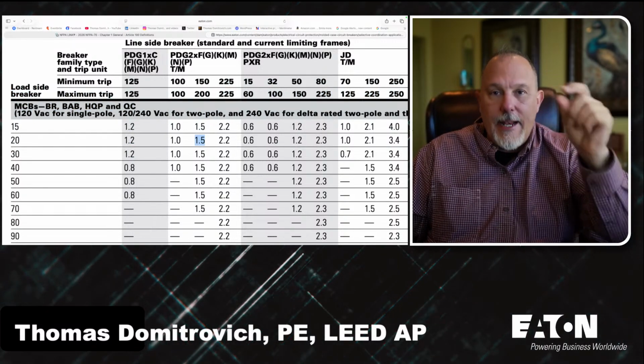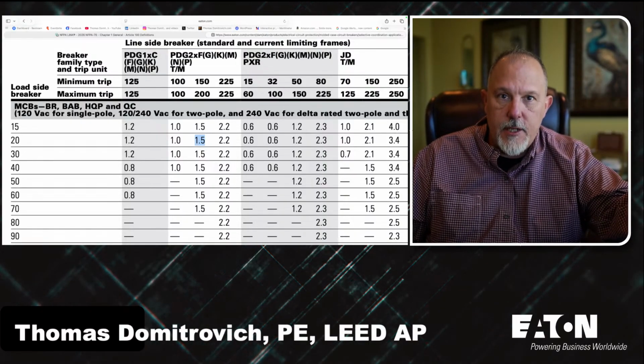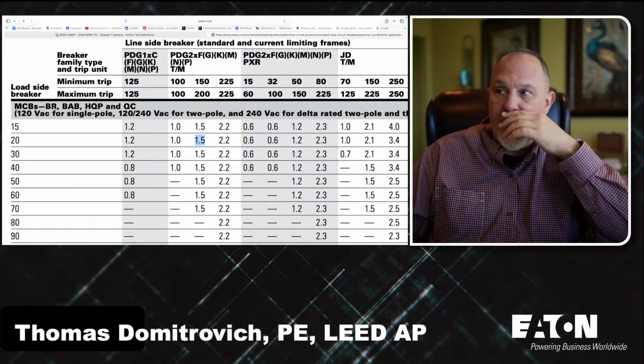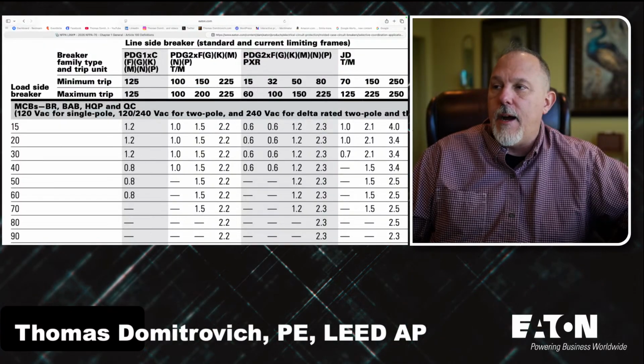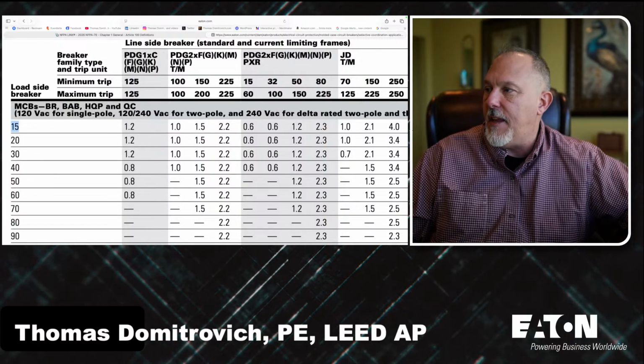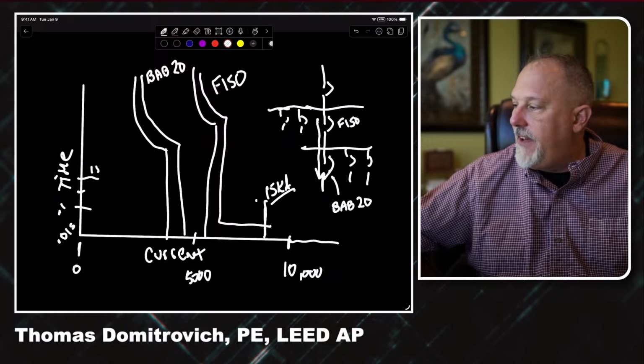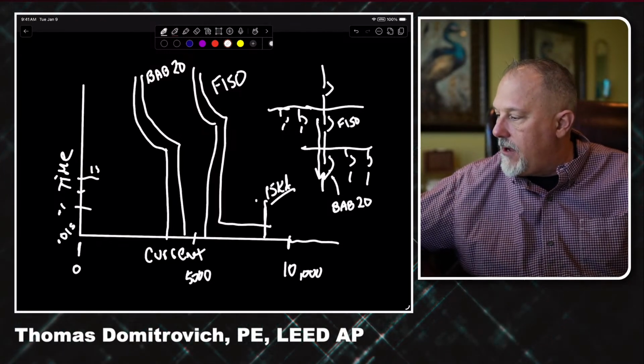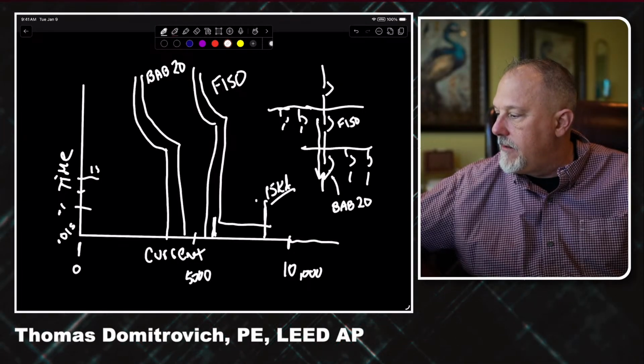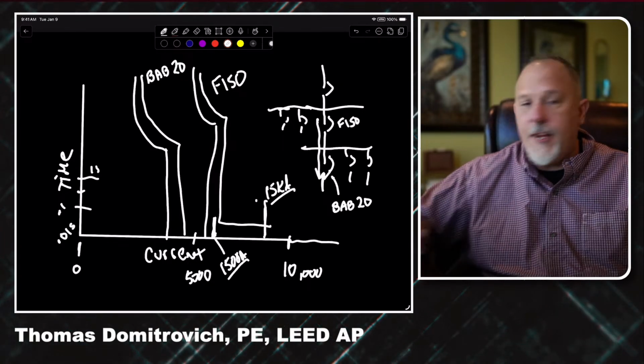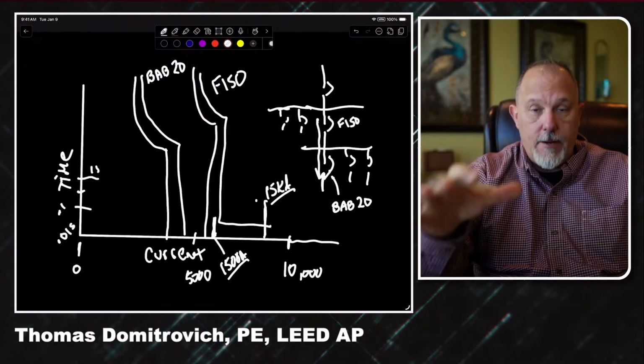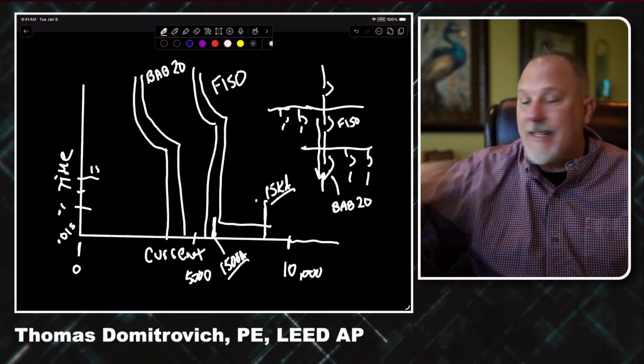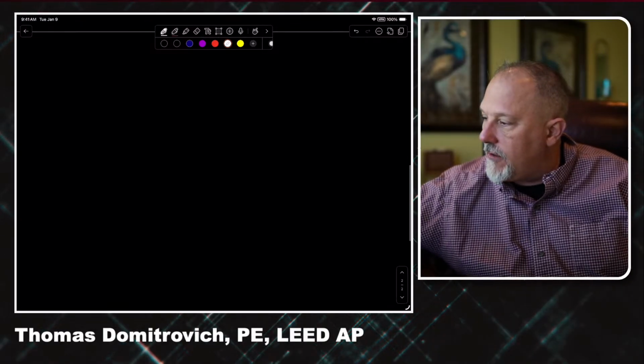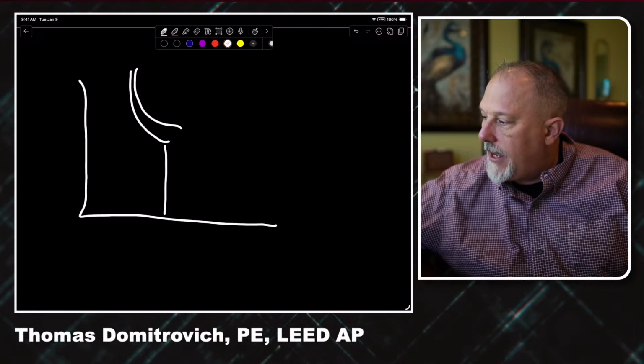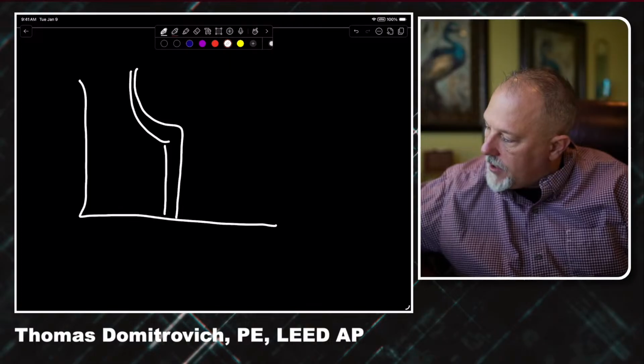That tells me that any current over 1,500 amps is going to open both circuit breakers. We've tested these in the lab. And in fact, it tells me that for that 150 amp breaker, I have up to 1,500 amps for everything from a BAB 15 to a 70. So now you know, without a shadow of a doubt, that for an F-150 and a BAB, the cutoff is somewhere around 1,500 amps. Any current greater than that, I'm going to trip them both. And that, Robert, tells you what's going on down below, because if you looked at a BAB curve, if I drew this curve, and I know it cuts off right there, but if I drew it further down below, you would see something like this.